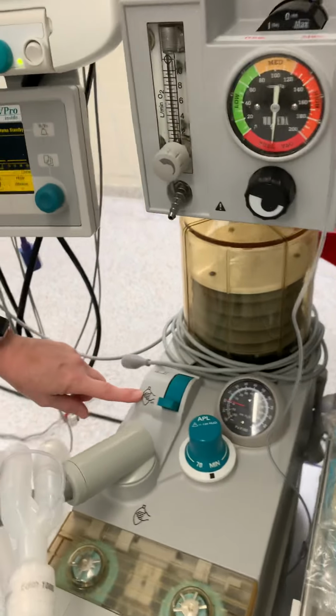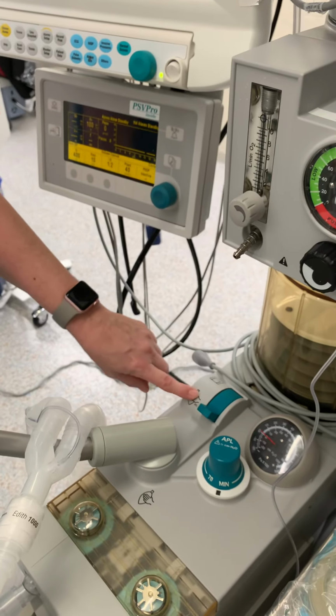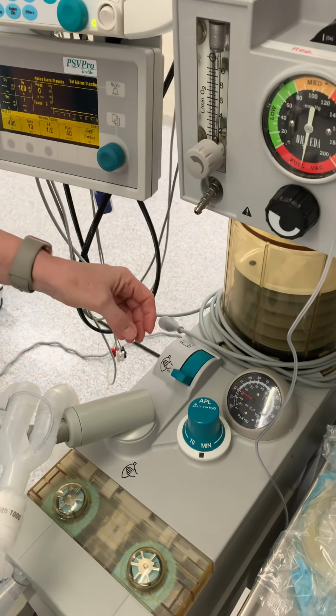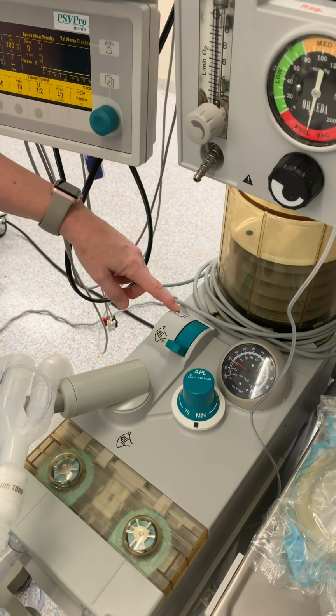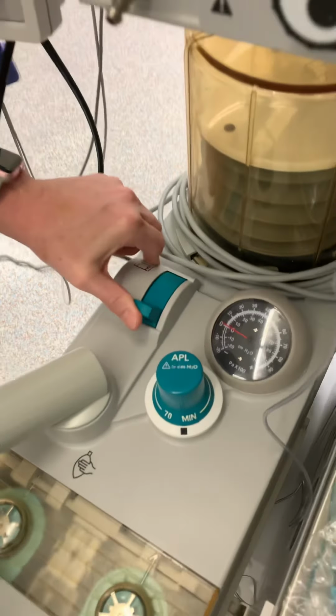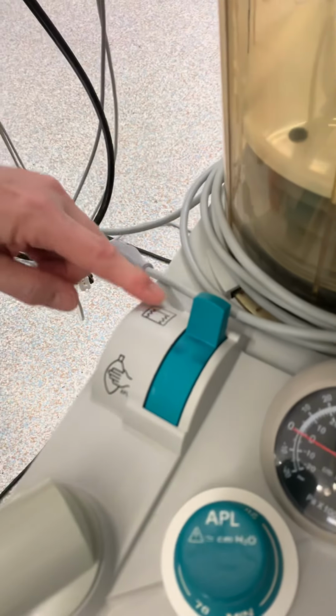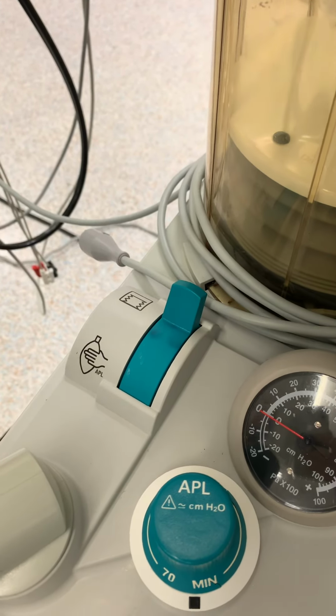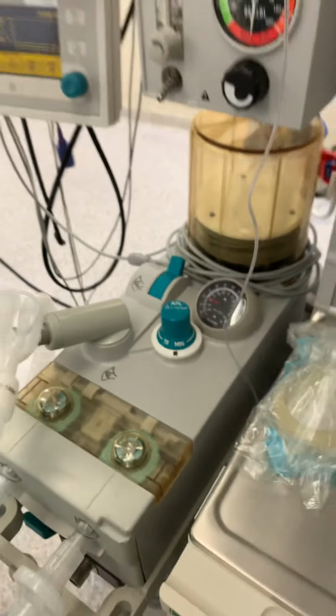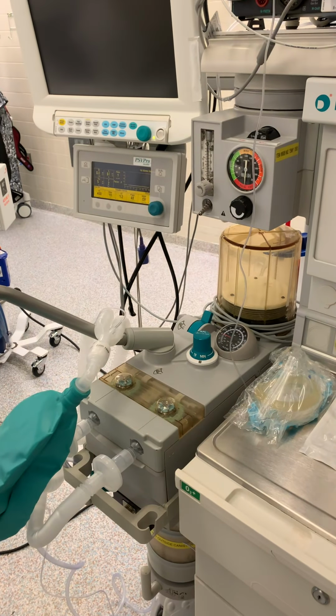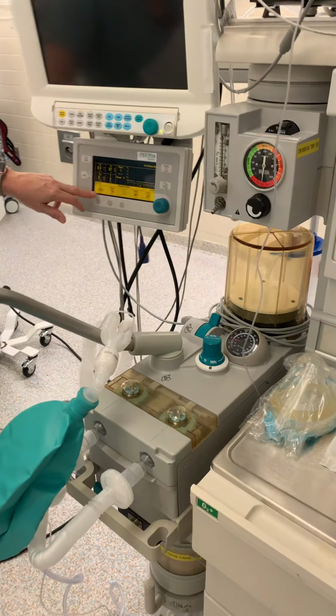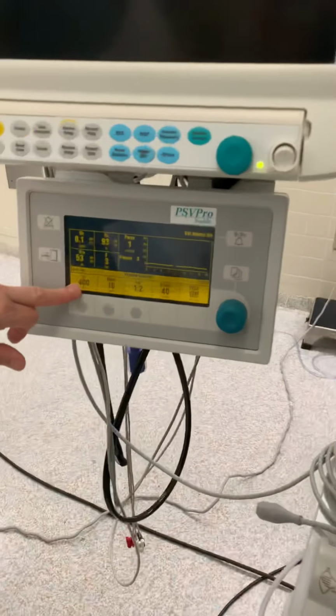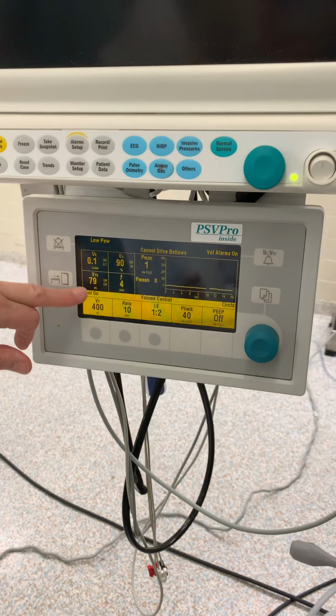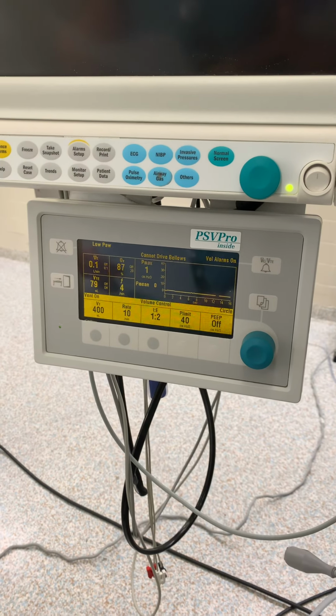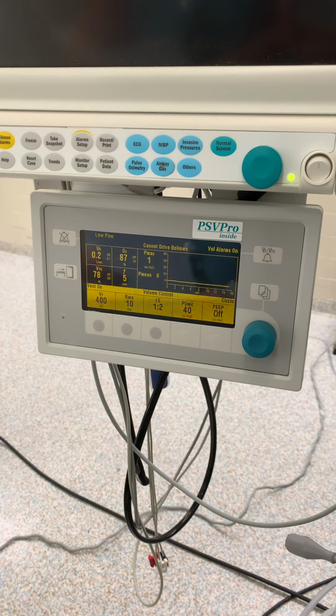The next step is you will always be on a bag with the hand on the bag. This is manual breathing. When you want to go to controlled breathing, you need to flip to the bellows sign, which means you flip to the ventilator. So now we're going to give the ventilator a chance to equilibrate, and what we want to see is that what we dialed in, which is 400, is what we get back at 400, and that takes just a few minutes.